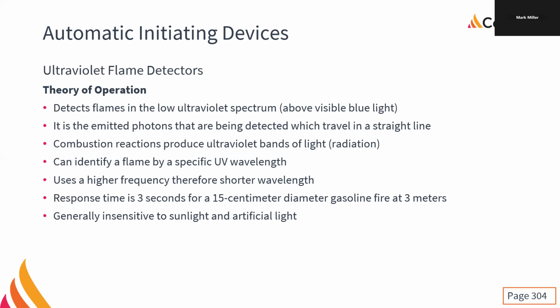Right, so we're using the low ultraviolet, just above the visible blue light. We're looking at the actual emitted photons that are being detected, which travel in a straight line, and so it can identify a flame by that specific wavelength. It's a higher frequency, so it has a shorter wavelength. Officially, the response time is 3 seconds for a 15 centimeter diameter gasoline fire at 3 meters.